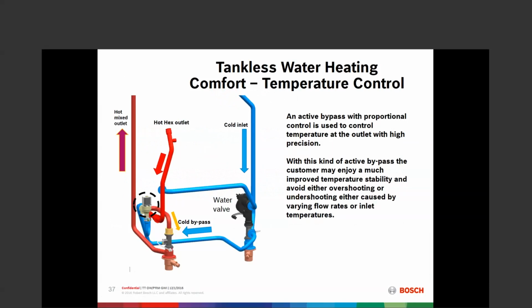At that T, it goes up through the water valve. So that's the primary water valve. That's one that senses the flow. There's an NTC thermistor here watching the temperature of the water coming in. Then it runs over here to this valve. Cold water comes in, goes through the heat exchangers, comes out of the heat exchangers, and it'll be overshooting set point a little bit. We're measuring that overshoot again with another NTC thermistor that sits right here on the outlet of the heat exchanger. It sits in there in a well and looks at that temperature.